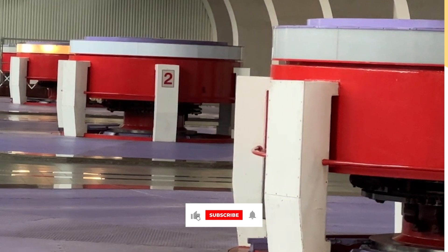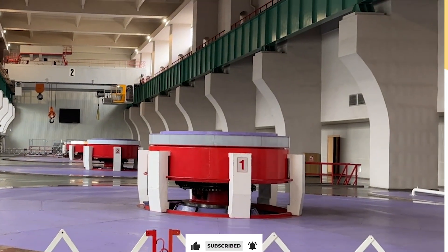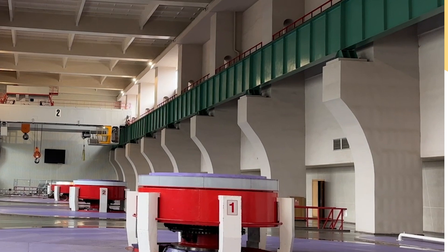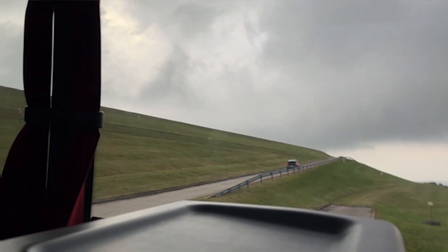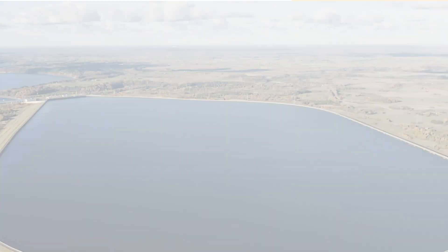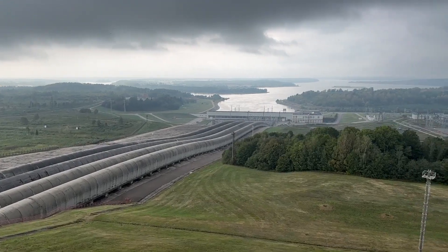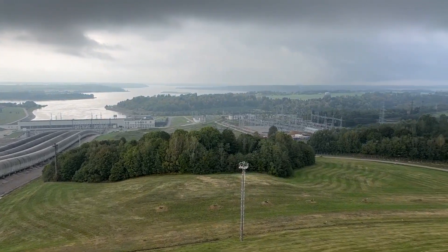What you see here in this room are the hybrid pump-slash-turbines, which pump water uphill but can spin in the opposite direction to generate electricity. We also got to go up to the basin, which essentially stores the potential energy. We were told that the Kaunas Lagoon was not allowed to fluctuate by more than 20 centimeters under normal operation of the pumps and generators.